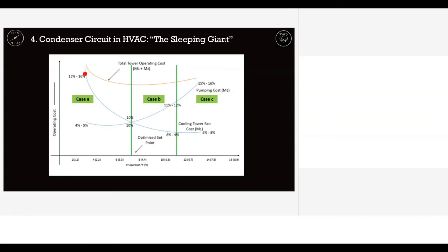So there is M1 and M2, two parameters you should learn. One is the cost of the cooling tower operation, that is M1, this line, and there is the cost of condenser pump operation, M2. These two things are usually in a centralized air conditioning plant a flat line, nothing changes. Both are constant speed, and some places people use the variable speed cooling tower with the VFD mounted on that. But what Smart Joules proposed, through our ideas, innovations, and continuous experimentation at our sites, is the ideal operation of the condenser circuit with the pump and the cooling tower, where the condenser pump is on VFD and the cooling tower is also on VFD.